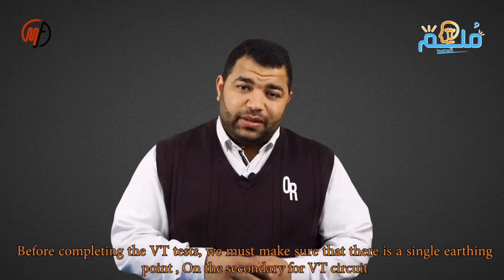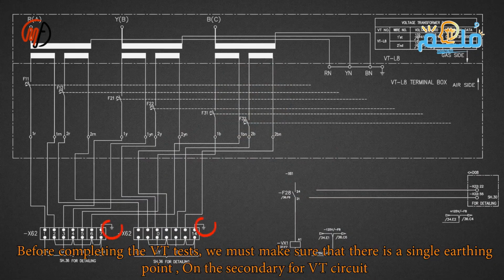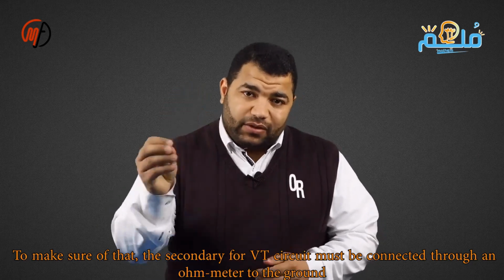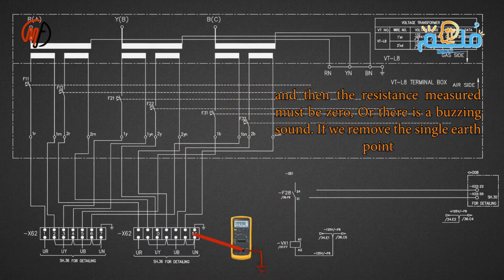Ensure a single earthing point on the secondary circuit of the VT. Connect the secondary circuit of the VT through an ohmmeter to the ground. Resistance should be 0 or buzz. Remove earthing, resistance not 0, buzz gone.